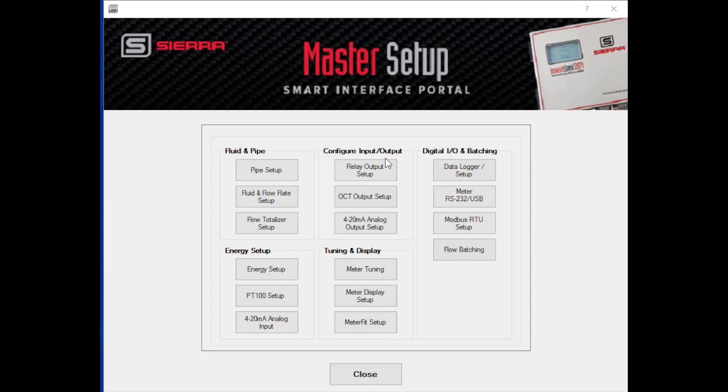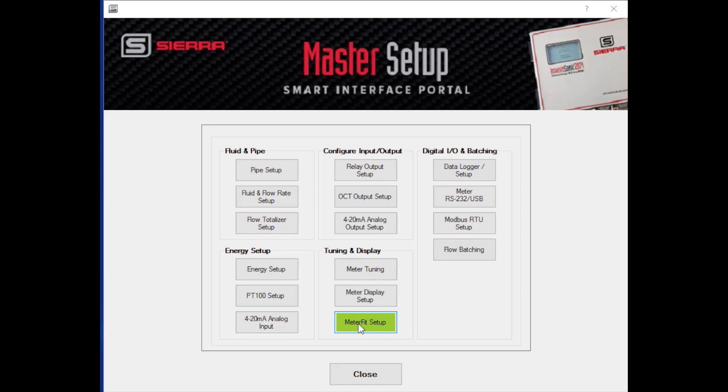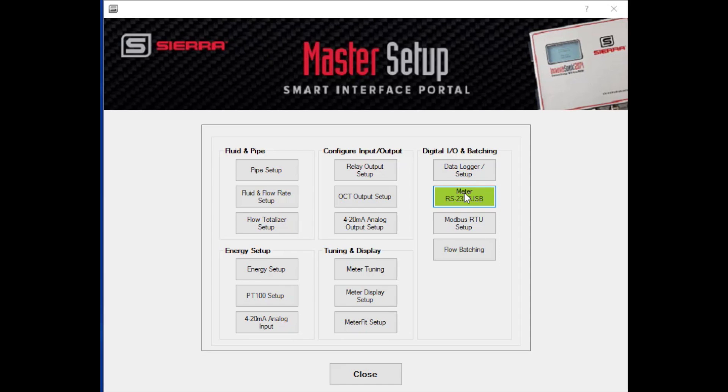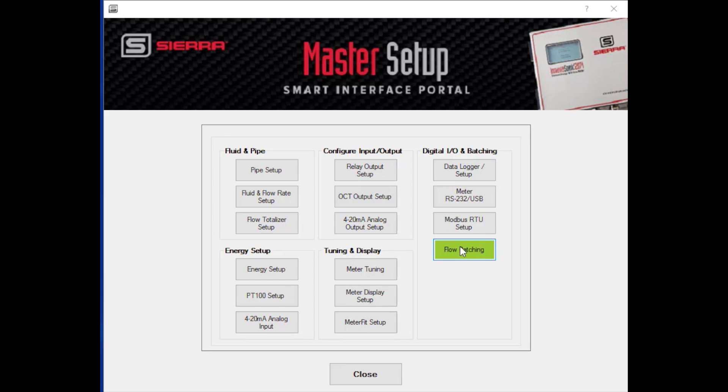We've got various inputs and outputs that you can configure. We have a relay output, an OCT, open collector transistor output. And our 4 to 20 analog outputs, as I mentioned, we have three. So you can set those up. Meter tuning, meter display, meter fit. Those are similar to what we looked at when we did the QuickStart. But you can look at them in more detail here. And finally, our digital communications inputs and outputs. We have a data logger. You can set that up to look at data over time and look at graphing. We have our RS-232 port. You can set up the various baud rates and so forth that you're using. Same with Modbus. And finally, flow batching. We can use flow batching to use our relay to turn external valves on and off, turn the totalizer on at a certain point and turn it off at a certain point, and other things. So the master setup menu gives you more in-depth access to those various features.